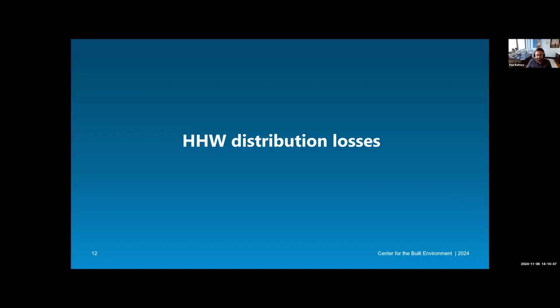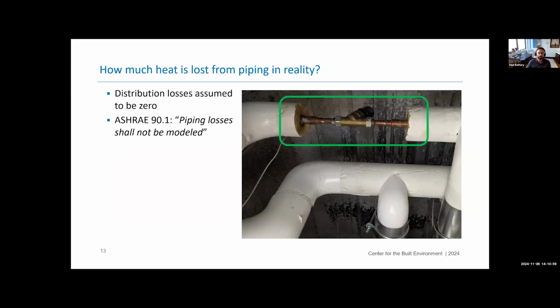So the last element that I wanted to highlight here was that these systems have some distribution loss, heat loss in the system, that isn't being accounted for in how we assess these systems today. And one of the reasons that isn't accounted for is because standards like the ASHRAE 90.1 standard say that piping losses shall not be modeled, right? And they're always assumed to be zero. But even in idealized conditions, there's still some heat loss through the insulation, right? And in almost every building I've ever seen, there are many sections of piping that look like this in the image you see up here. Exposed sections of piping around a valve or a fitting, or just poor installation, right?